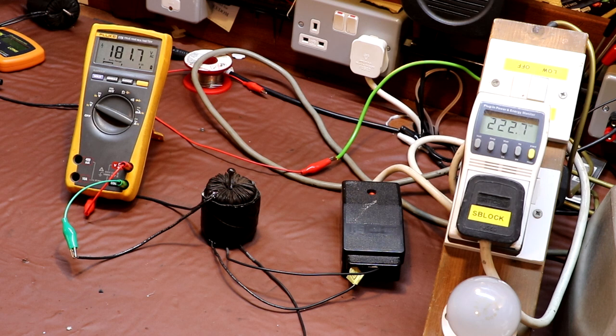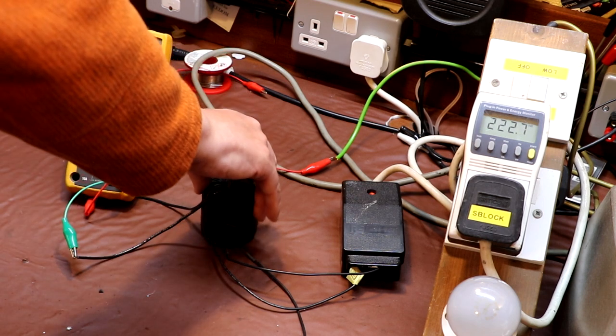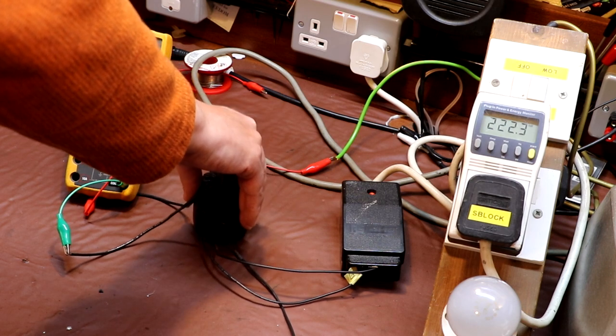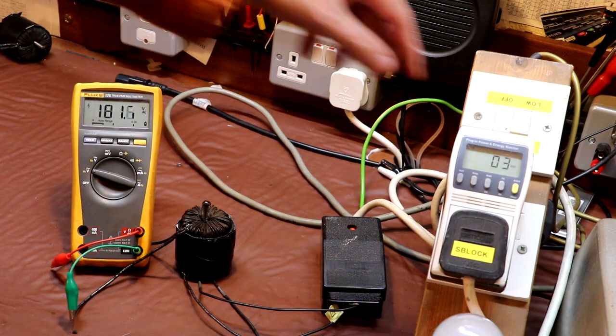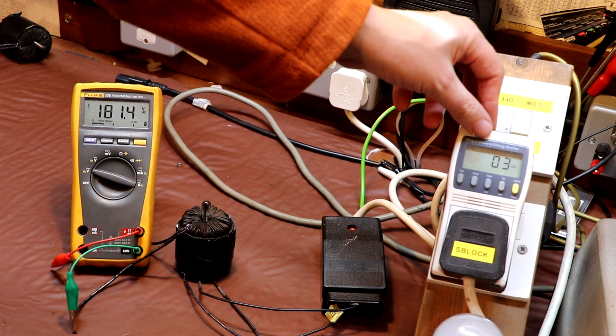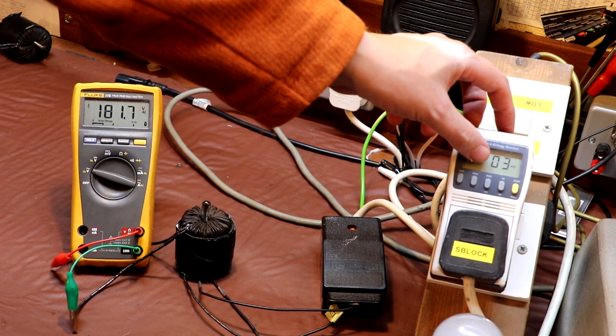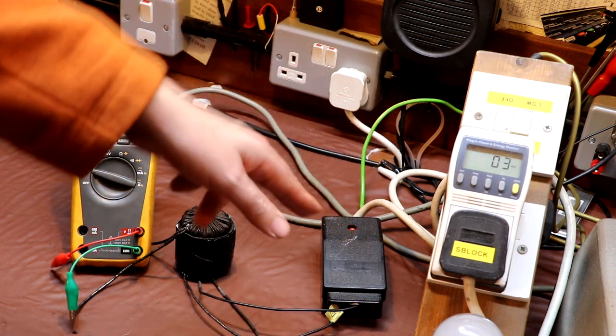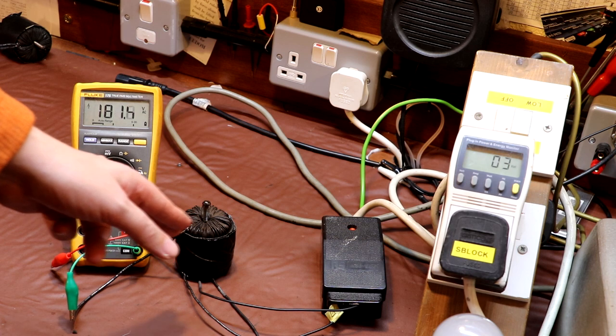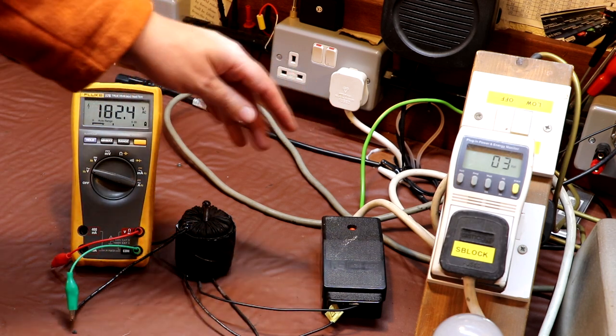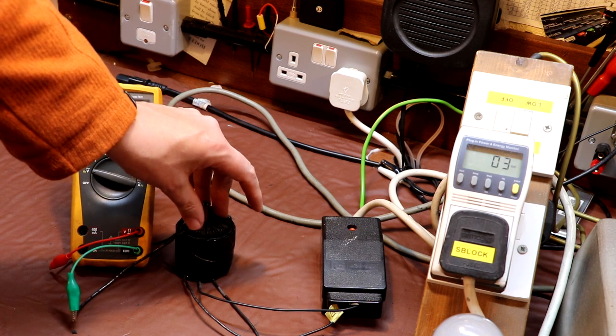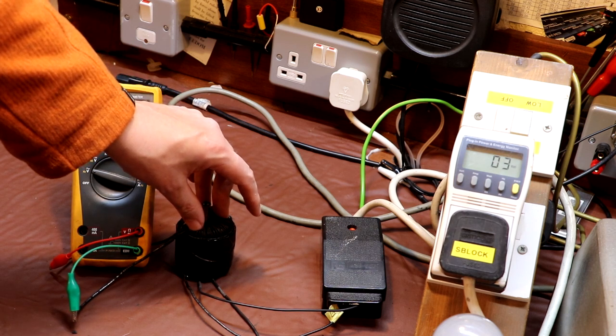So what that tells us is that we're putting energy into the transformer and we're not getting any useful work out of it because there's no load connected. This heat that we can feel is all wasted energy, it's inefficiency. If you swing in and take a look at our energy monitoring plug, it's showing 3 watts at the moment. So 3 watts of power are going into this transformer and not doing any useful work. All they're doing is heating up the transformer and going straight up the chimney. So we've got 3 watts of power there, which is just heating the world.